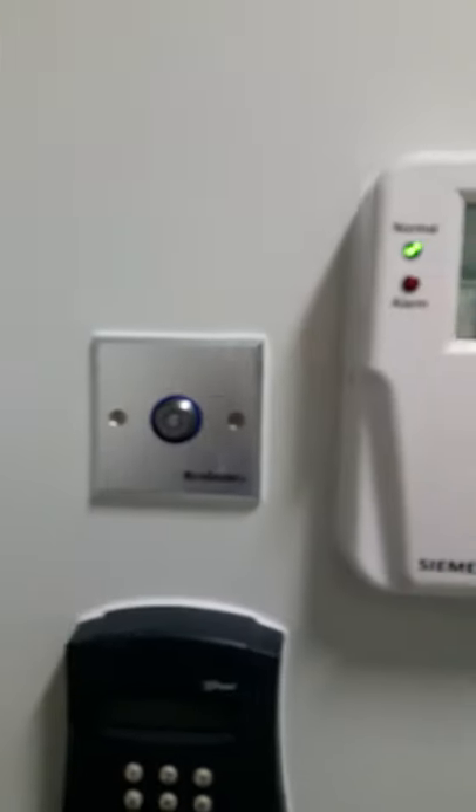This room is positive and the air in this room is basically pressurized to keep the pathogens intact in the next room. The next room is at negative pressure — you can see it has a negative pressure of 24.2 Pascals. We have a second security procedure. This is the negative pressure area. We have the control rooms which control all the fans and the HVAC systems, and a monitor for CCTV for security protocols.